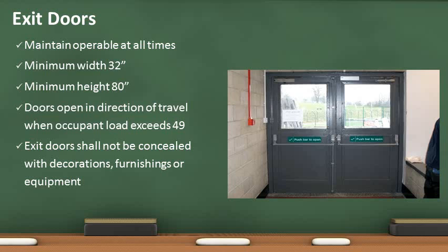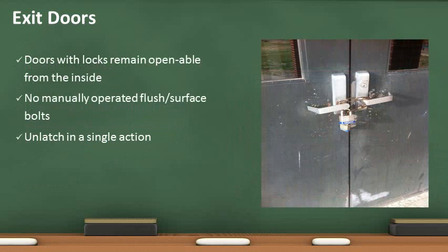It is important to note that exit doors must not have anything attached to them or within 3 feet, such as decorations or student artwork. This includes classrooms. Exit doors are required to be opened from the inside without a key or special knowledge. No chains or any other obstructions are permitted.